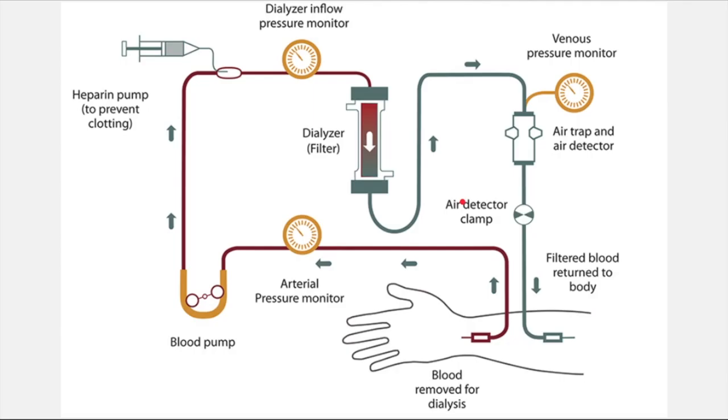Okay, next is then the dialysate inlet. So the dialysate inlet is found here. It can be found right here, not on this top one, but rather here. So the inlet is found where the blood is coming out rather than going in. So the inlet is here, and this is where the fresh dialysate solution goes into. This draws out the waste from the blood. So this is the dialysate inlet.